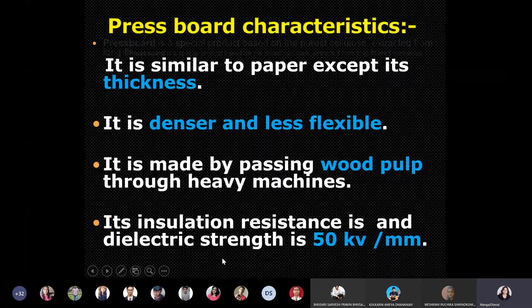What is the meaning of this? You take a pressboard of 1 mm thickness and keep it across the electrode, and go on applying very high voltage across it. At 50 kilovolt, you will find your pressboard has broken down. Means what? 50 kilovolt per mm is the highest dielectric stress pressboard can withstand without destruction of insulating properties. So pressboard will not allow any current to flow until your voltage is less than 50 kilovolt. But when voltage becomes 50 kilovolt, immediately current will start flowing. Means there will be a conversion from insulating material to conducting material, and you will say pressboard has broken down. So that is the dielectric strength.